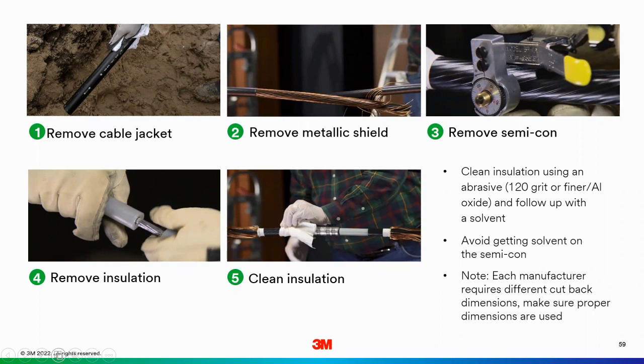And then, next step, number 4, removing the insulation. And then cleaning the insulation is a very important step. You're going to want to do a light sanding just to take out any imperfections. But if you have any deep grooves, nicks, cuts, anything in that insulation, this isn't something that should be attempted to be sanded out. Most likely, you're going to have to start over if the groove is deep enough. But just a rule of thumb, when you're cleaning, you want to clean away from the semicon on your insulation, never touching the semicon with your solvent wipes, because you don't want to be dragging that semiconductive material, the black layer, onto the insulation, because that's just going to lead to problems down the road.